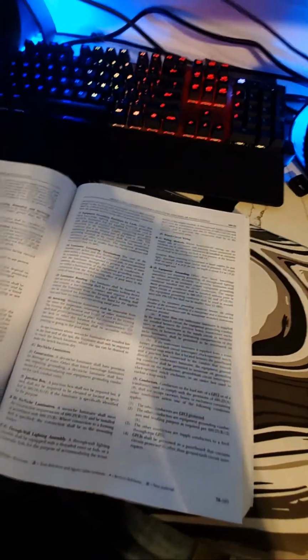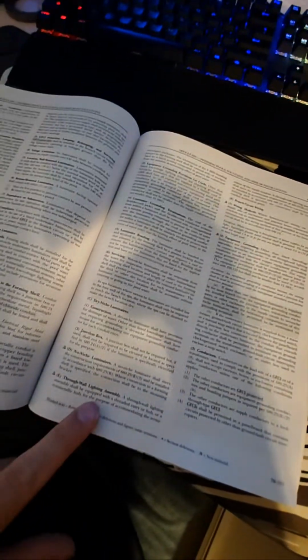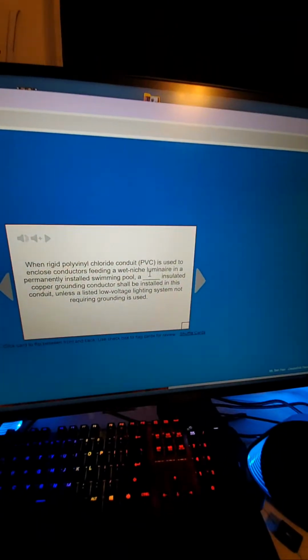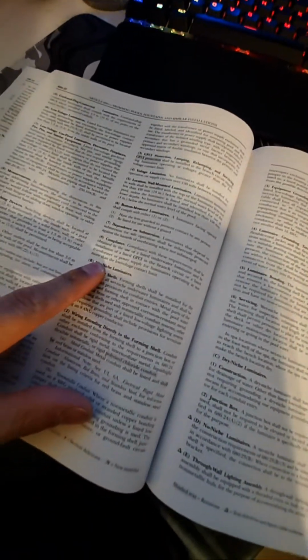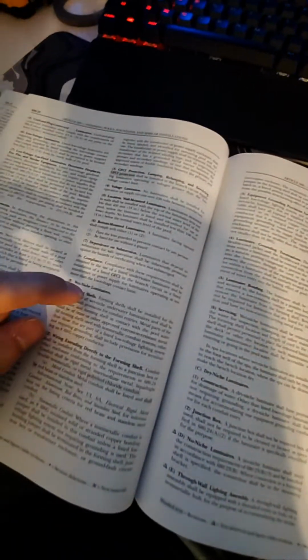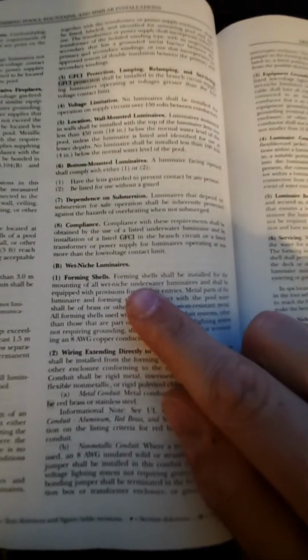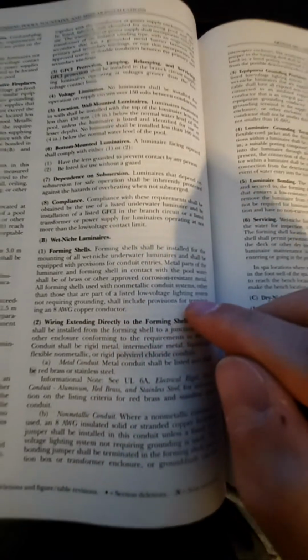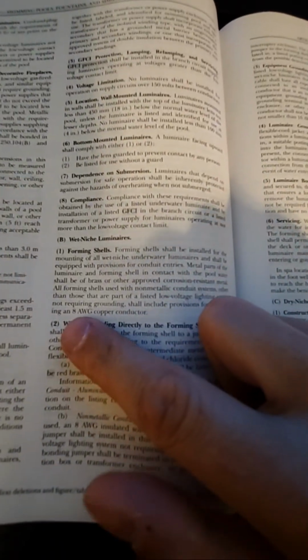More receptacles. There's permanently installed pools. Luminaires there. There's the wall lighting. Let's go over here to the forming shell because that's what this is. It's a wet niche. So there's wet niche there. So we are very close. We know the wet niche right there, and our answer is actually right here. So what it says here, it's going to be number 8. But what it's going to say, shall include provisions for terminating a number 8 AWG copper conductor.